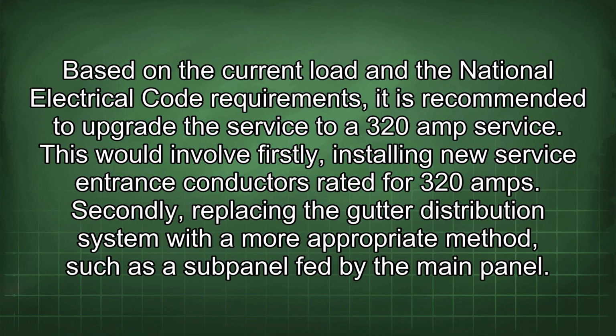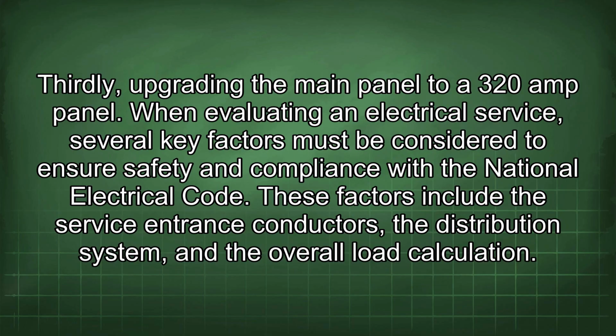Based on the current load and the National Electrical Code requirements, it is recommended to upgrade the service to a 320 amp service. This would involve, firstly, installing new service entrance conductors rated for 320 amps. Secondly, replacing the gutter distribution system with a more appropriate method, such as a subpanel fed by the main panel. Thirdly, upgrading the main panel to a 320 amp panel.